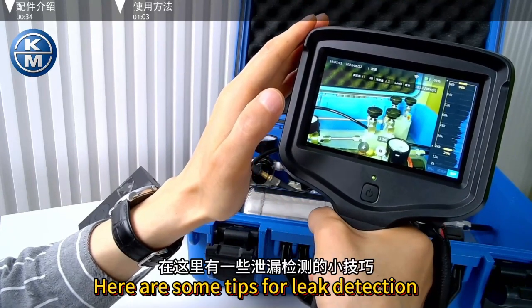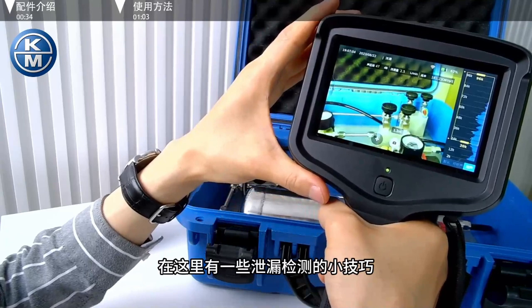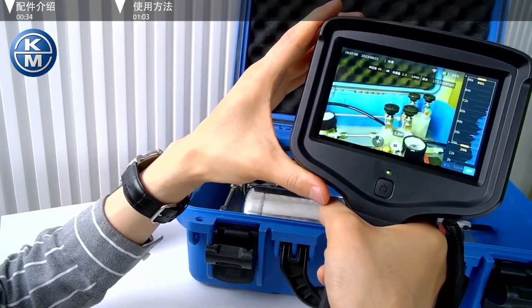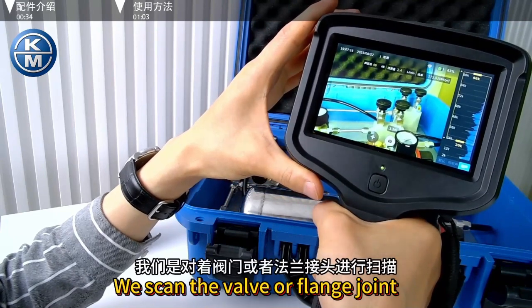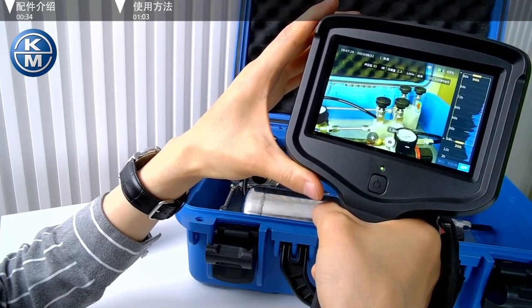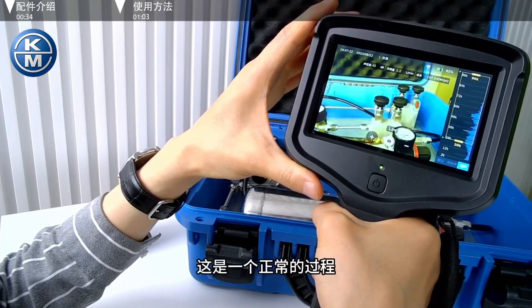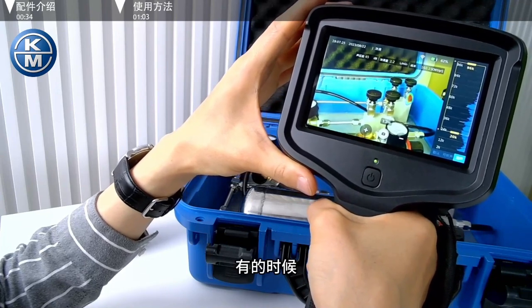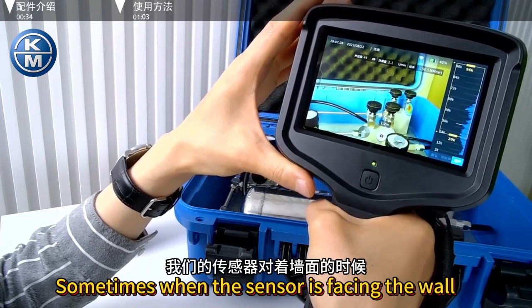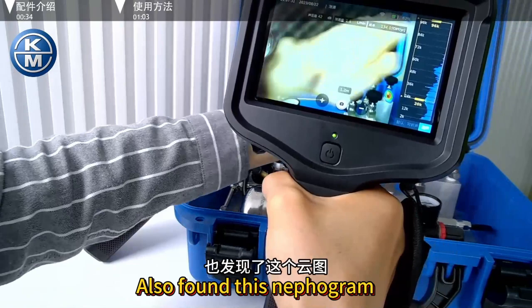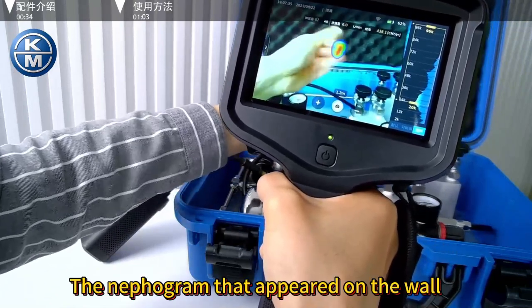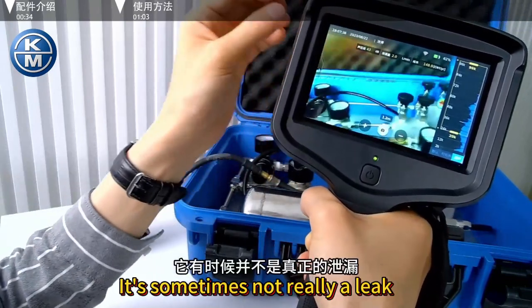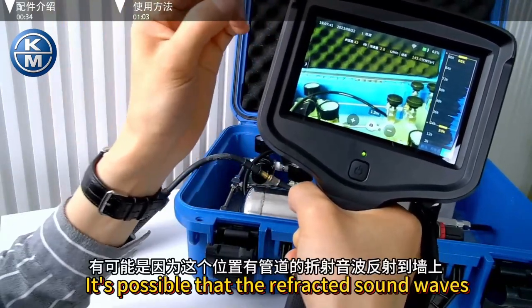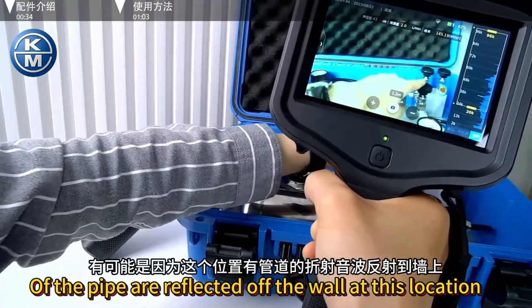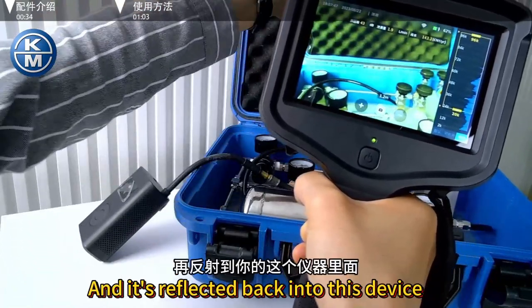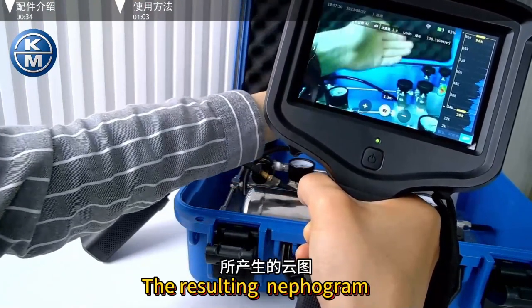Here are some tips for leak detection. Sound can be refracted. We scan the valve or flange joint. Sometimes when the sensor is facing the wall, we also find this sound cloud image appearing on the wall, and it's sometimes not really a leak. It's possible that the refracted sound waves of the pipe are reflected off the wall at this location, and reflected back into this device, producing the cloud image.